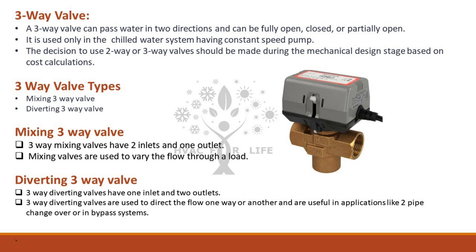Three-way valve types include the mixing three-way valve and the diverting three-way valve. Mixing three-way valves have two inlets and one outlet and are used to vary the flow through a load. Diverting three-way valves have one inlet and two outlets and are used to direct flow one way or another, useful in applications like pipe changeover or bypass systems.